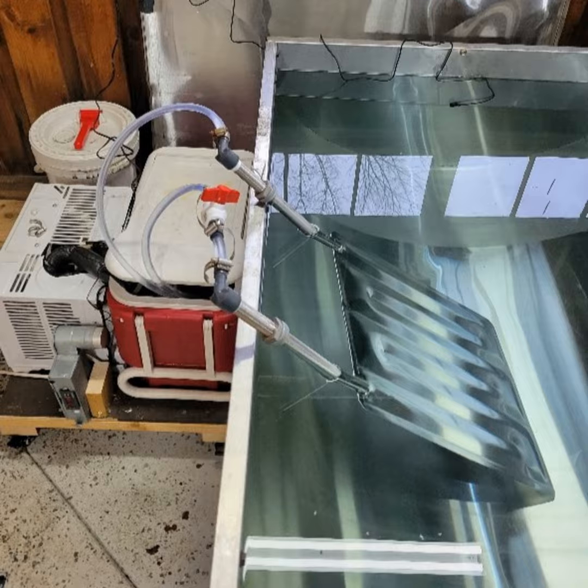So you carefully pull that cooling coil out and submerge it into a plastic picnic cooler. The cooler creates a tank that you can fill with a glycol water solution, an insulated little tank. It doesn't have to be a picnic cooler, they just happen to work well, and a lot of people have them lying around. So that coil goes down into the cooler, and you fill it with the glycol water solution.